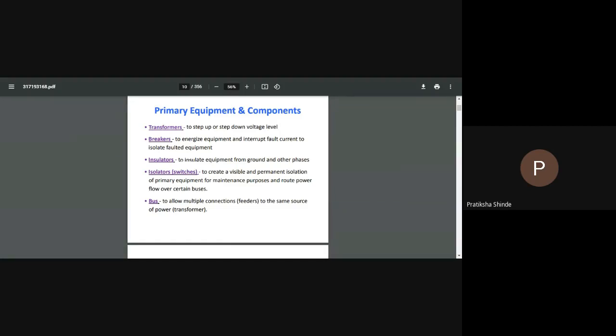Now what is given in that? To create a visible and permanent isolation of primary equipment for maintenance purposes, and to route power flow over certain buses. Whenever it is connected, power flow is healthy; whenever disconnected, there is no power flow. Whenever you want to take the system or your transformer into maintenance, you can isolate it using the isolator switch.